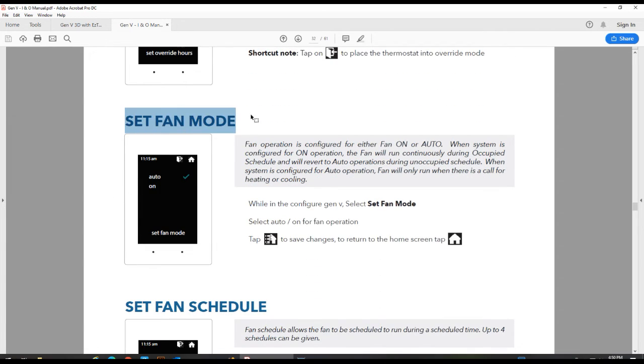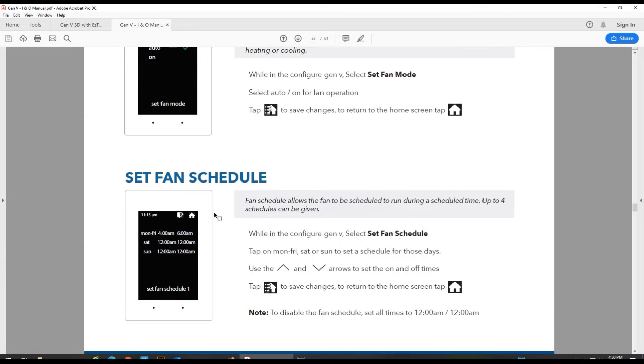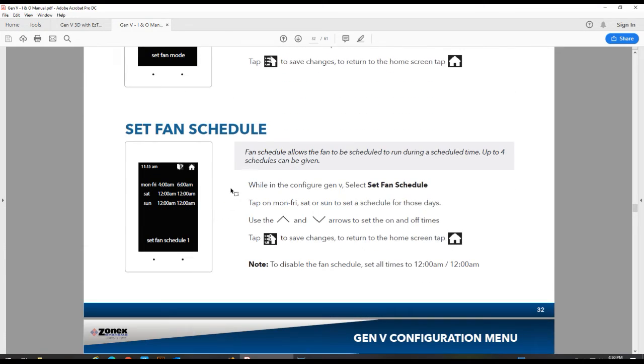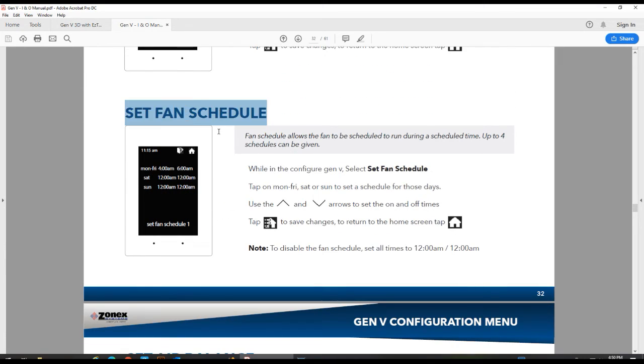Setting your fan mode. If you want to run your fan on or constant during occupied hours, you can go ahead and change it to the on, and then during unoccupied hours, the fan will run in auto mode. So make those adjustments according to your requirements in the area or your region.